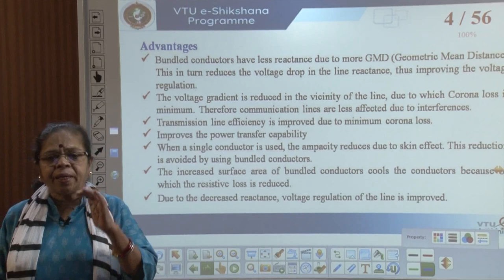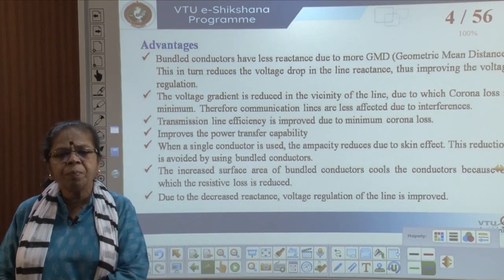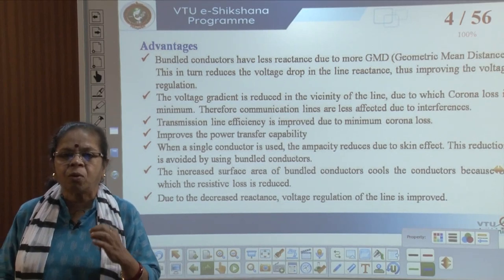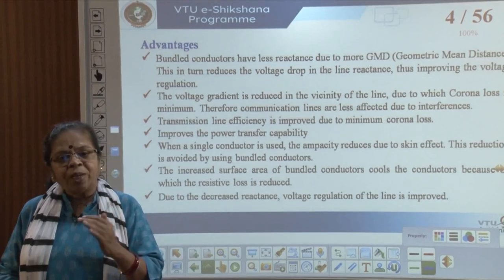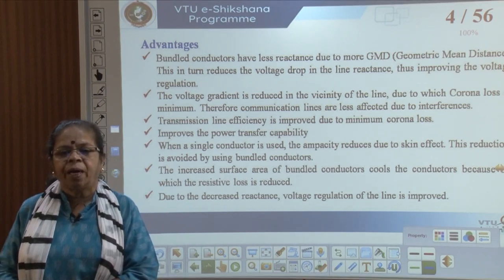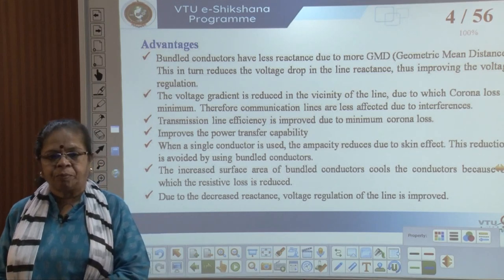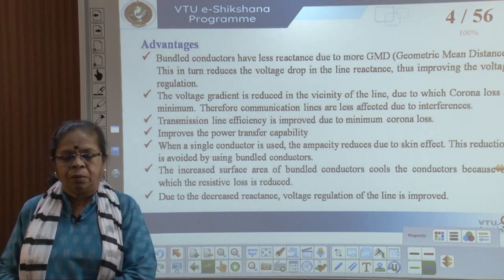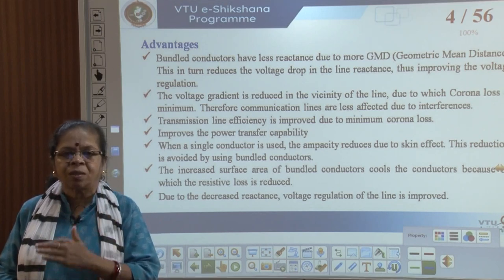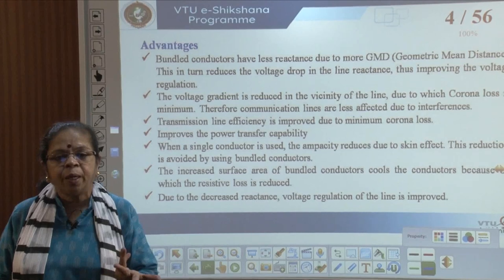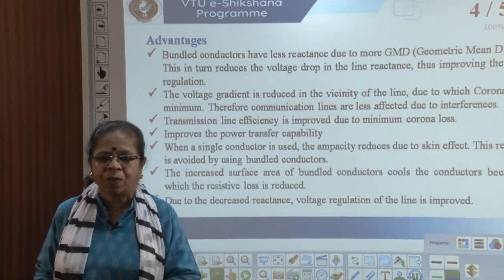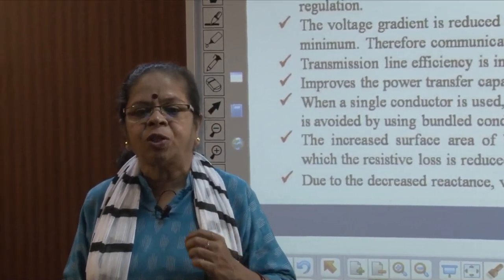The second advantage is that the voltage gradient is reduced in the vicinity of the line. Voltage gradient means voltage per centimeter. The breakdown of a material depends on the voltage gradient, so if the voltage gradient is reduced, there are lesser chances of breakdown of air, and therefore the problem of corona and interference with communication is reduced. Since corona reduces, the loss also reduces, the transmission efficiency improves, and the power transfer capability also increases.